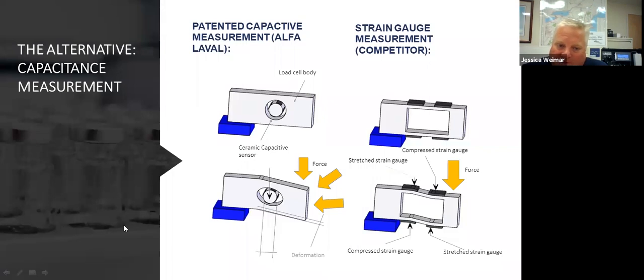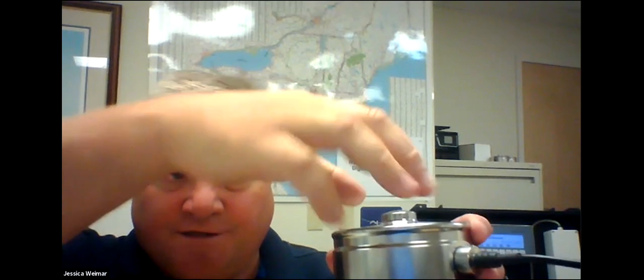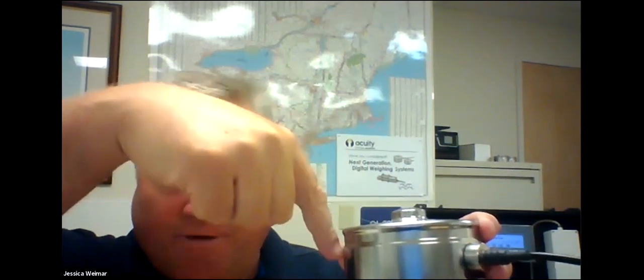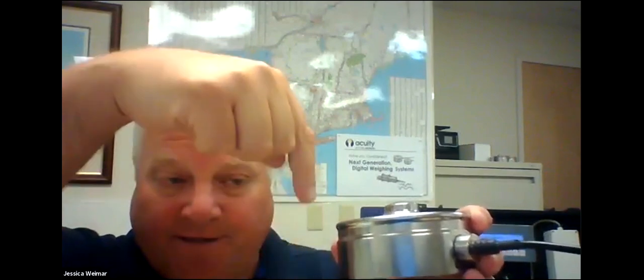And again, I showed you two different types of cells. And I'll go back and show you that again. If you look here, this is a compression or a ring style cell. It's harder to understand in this cell, but the same concept happens. As you apply load to the top surface of the cell, this entire surface is deflected down inside the body, and it's measuring a distance change inside compared to the adjacent ceramic sensor. It's easier to understand with this one because you can simply see that as you deflect the cell, you can envision how this is able to measure the deflection. But the concept is the same between the both of them. They measure that internally. Okay, I hope that's clear. If it's not, please let me know.